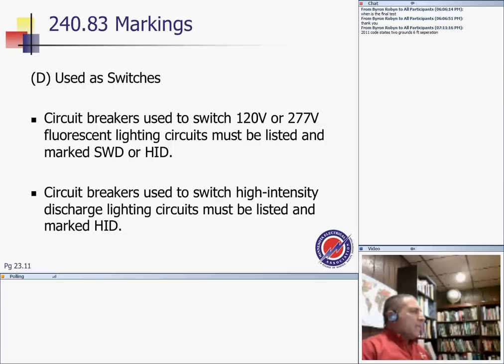Marking used as switches. If I have a circuit breaker, the question would be, can I use the circuit breaker, guys, as a switch? No problem. A circuit breaker is used to switch 120 or 277. If switching fluorescent lights, because of the inrush, it has to be rated as a switch. If it's switching high intensity discharge lights, they have to be marked HID, high intensity discharge lamps. The reason is that fluorescent and high intensity discharge lamps have inrush.